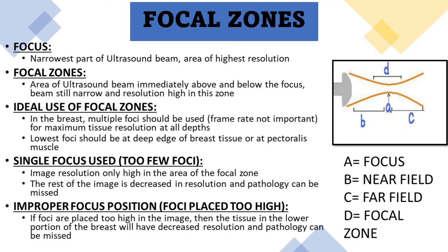In the breast, multiple foci should be used for maximum tissue resolution at all depths. This slows down the frame rate, but in standard breast imaging, frame rate is not as important. The lowest focus should be at the deep edge of the breast tissue or at the pectoralis muscle. When only a single focus is used, image resolution is only high in the area of the focal zone, and the rest of the image has decreased resolution, so important pathology can be missed.